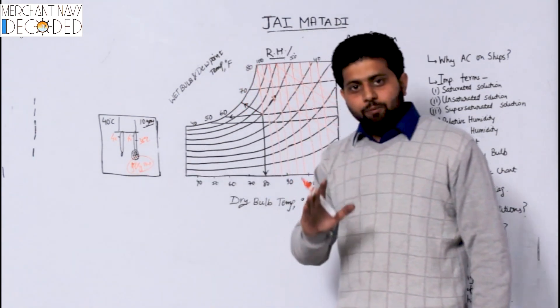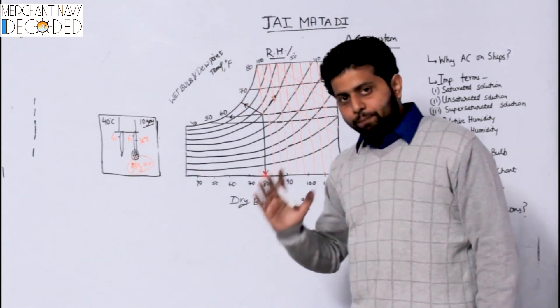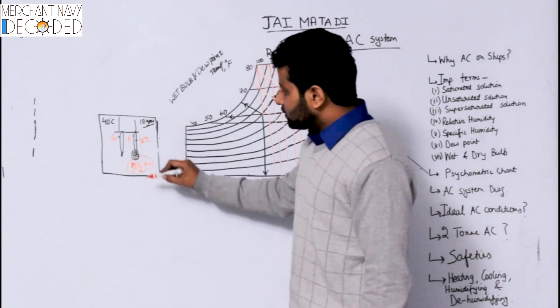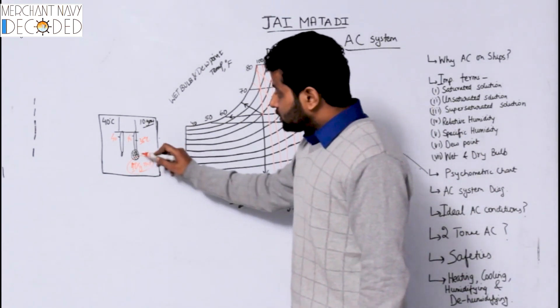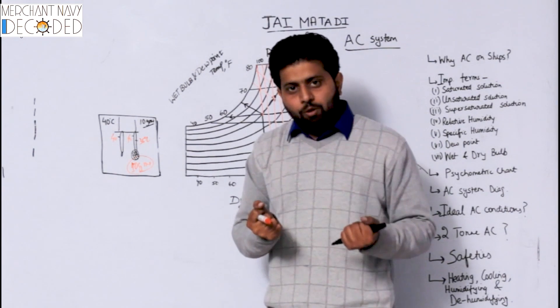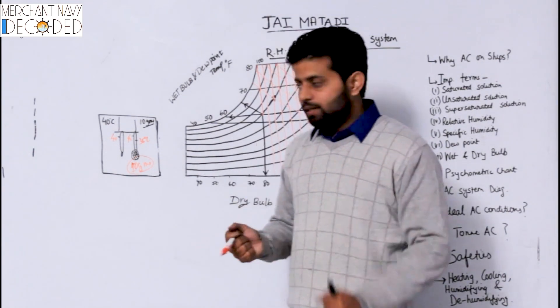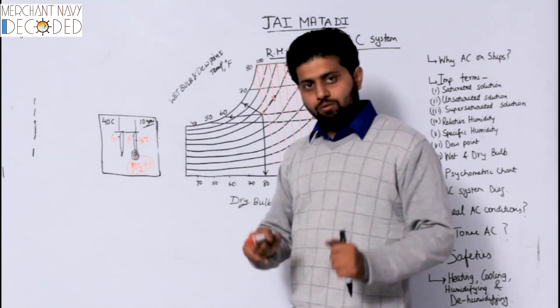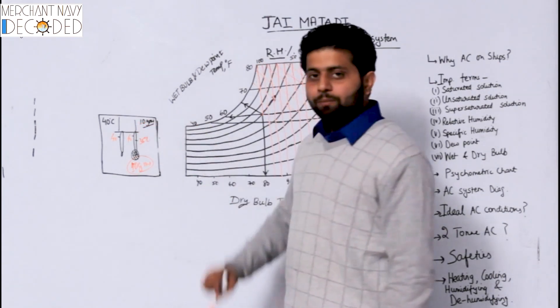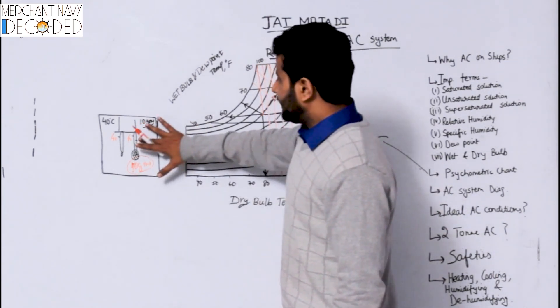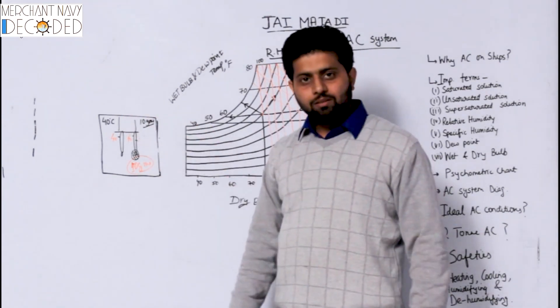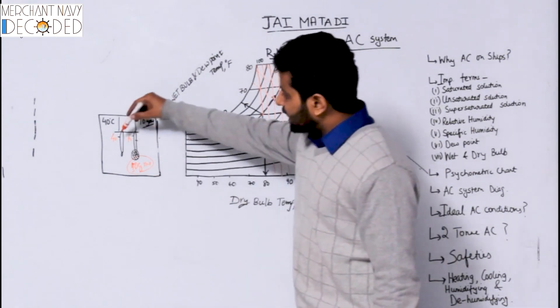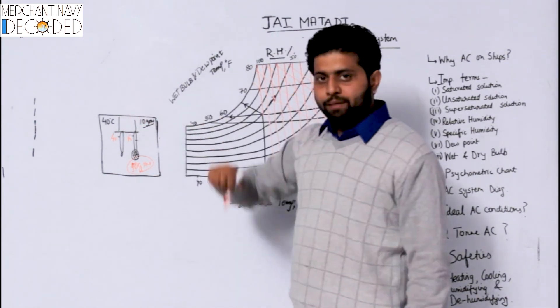That is, relative humidity is 100%. In this case, the room is not hungry of any moisture — it does not want more. Will this water evaporate? No. Will the temperature of this thermometer come down? No. It will show 40 degrees only. So this means that by knowing the dry bulb and wet bulb temperature, we can get an idea of what the relative humidity is.